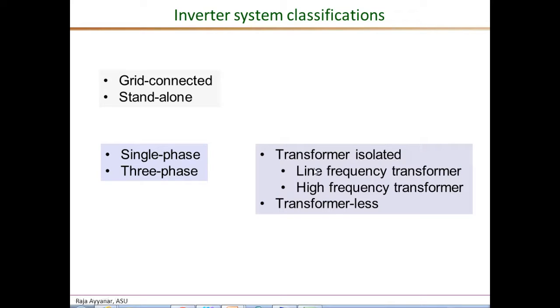Then you can have a classification based on whether the inverters have galvanic isolation using transformers or transformer-less topologies. Among those which have a transformer, you could have a line frequency transformer at 50 Hz or 60 Hz. Most high-power utility scale inverters employ line frequency transformers to step up the relatively low voltages of 400 to 600 volts RMS line-to-line to distribution or sub-transmission level voltages, while also providing isolation.